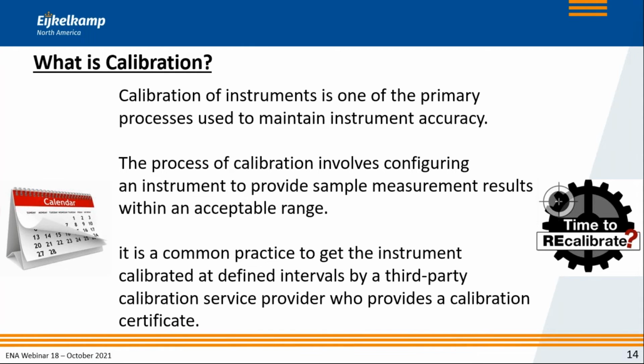And then it's common practice to get the instrument calibrated at defined intervals by a third-party calibration service provider who provides a calibration certificate, at regular intervals, and a calibration certificate. Those are the things that, when it comes to calibration, give you an understanding of why we do it, what it involves, and how it should be done.